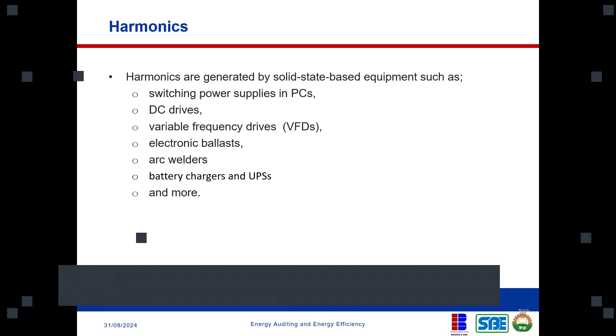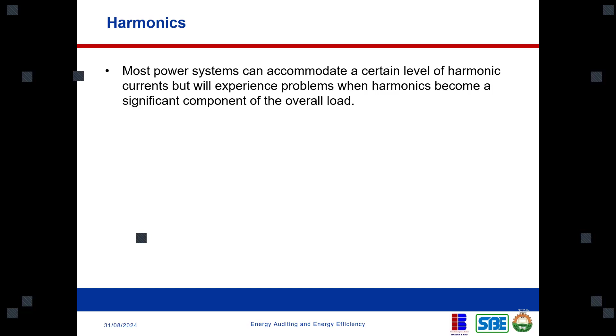Most power systems can accommodate a certain level of harmonics, but we experience problems when harmonics become a significant component of the overall load. Some of us may have heard that LED lighting introduces harmonics into the electrical system, and that's because LED lights are electronic equipment, different from the resistive filament we had in the past, the yellow light of incandescent bulbs, which are a resistive form of light generation. But LEDs are electronic equipment, and there has to be power conversion from AC to DC for them to function. In doing so, in some cases, they introduce harmonics, but much of the harmonic distortion they introduce can be negligible in most cases.